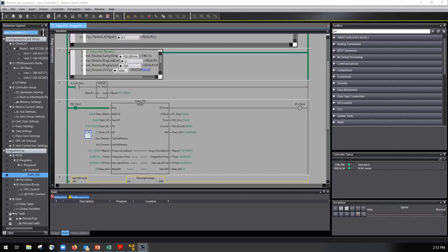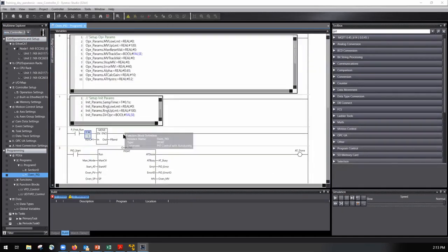If you're done with the material you wanted to cover today, I'd be interested in watching the troubleshooting. Yeah, that's all I really wanted to cover. I was going to show, and you guys don't need to play along with this, but like I said, the one thing I want you to remember about auto-tuning these things is this AT calc gain. So that was 10, right? That's very smooth, very slow to react. By default, it's really quick.